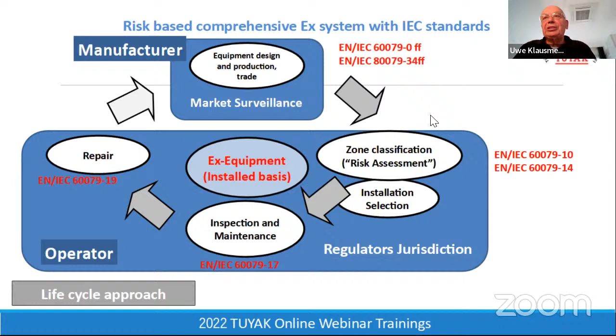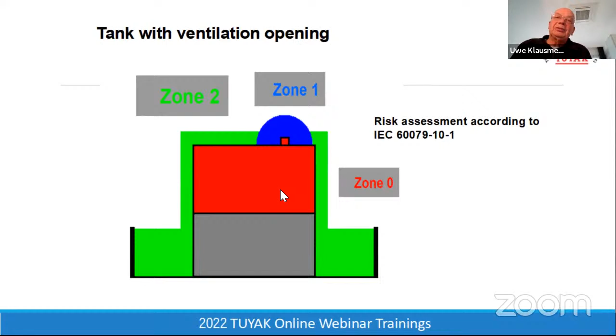Again, in this example, you have a tank and there is a liquid, a combustible liquid. Over the liquid, you have the zone 0 situation. So everything you have to buy here as equipment, a level gauge or whatever, a level gauge has to be equipment protection level 1. But we will come to it later. Don't be confused. We will detail all these wordings later by examples.